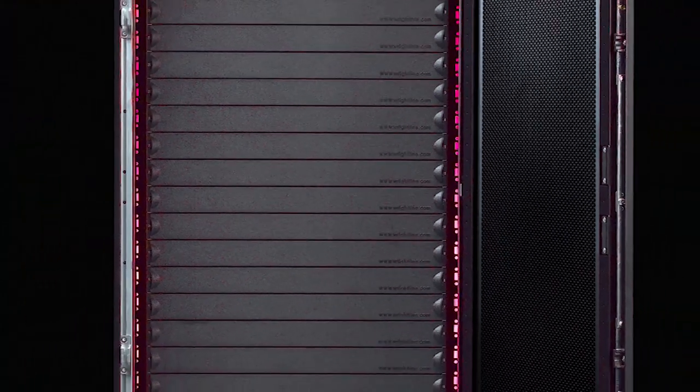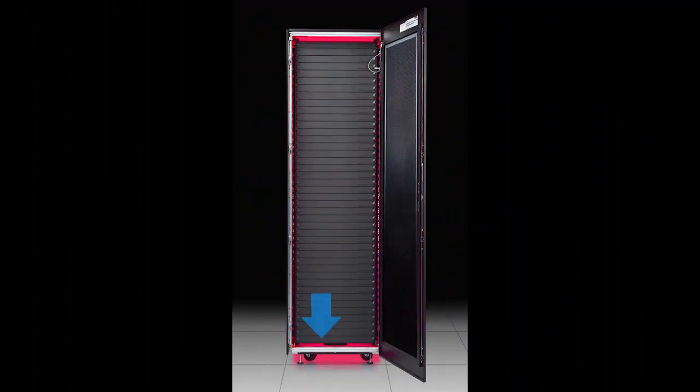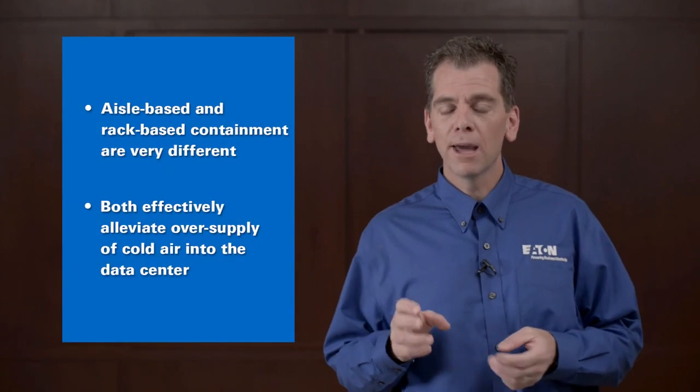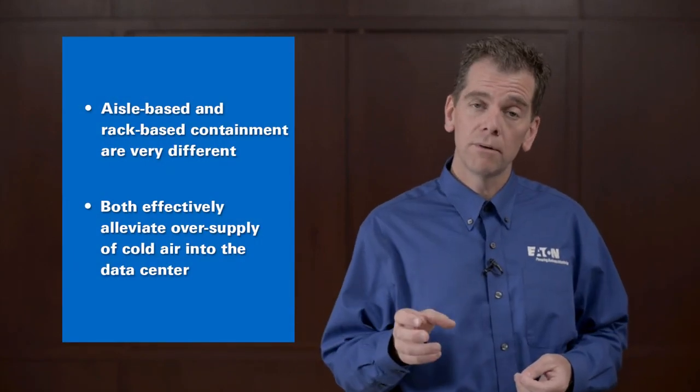Optimizing your data center for airflow management starts with the rack. There's 5 critical areas that the racks tend to leak. Beneath the frame, to the right and to the left of the internal rails, below those rails, and also above them. When you look at airflow management at the row level, it's a little different than the rack.